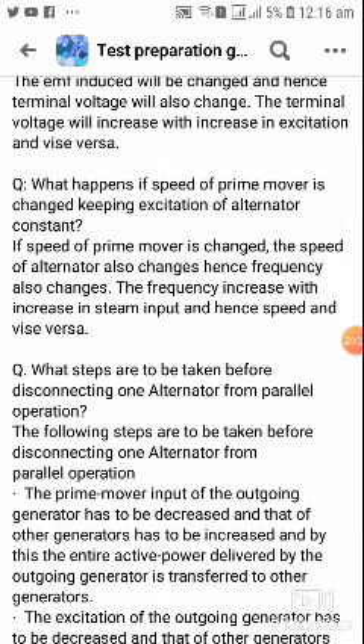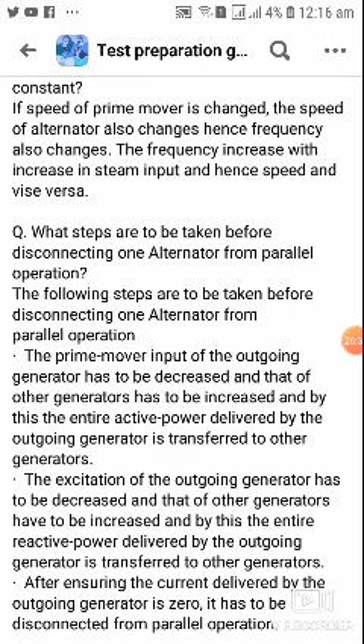Question number 48. What happens if the speed of prime mover is changed, keeping excitation of alternator constant? If the speed of the prime mover is changed, the speed of the alternator also changes, hence frequency also changes. The frequency increases with the increase in steam input and hence speed, and vice versa.